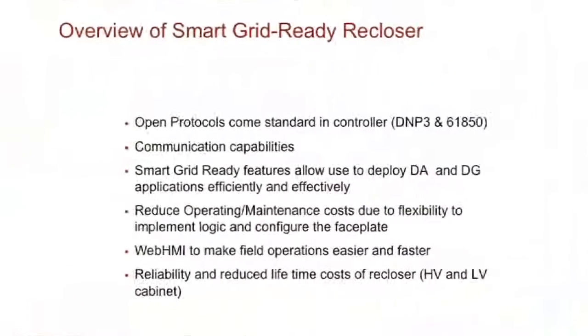I showed you a couple of slides where you could do a hybrid of different applications based on how you stage your deployment. So you don't have to worry about being locked to a particular technology. You can deploy a lot of the applications as long as you have open protocols and the hardware that you need to deploy these applications. Again, reducing operating and maintenance cost. Obviously, doing a lot of these FDIR schemes allows you to improve your reliability because you reduce the number of outages, the number of customers that are out, the speed with which you restore your customers, and you isolate the fault quicker. You can send your trucks a lot quicker to find where that fault was and fix it. So it helps you reduce your operating costs and maintenance cost.